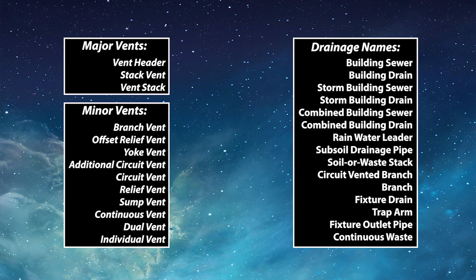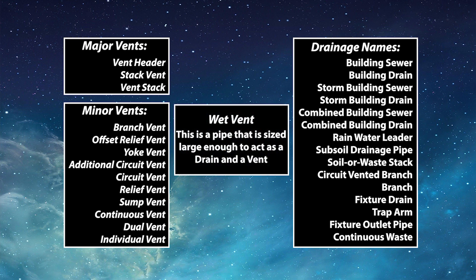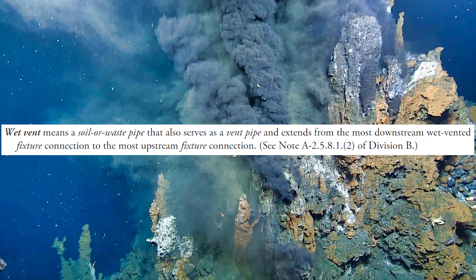In the plumbing trade we have many different types of drains and many different types of vents, but then we have one type of pipe that lands right in between the two. It's called the wet vent because it is a drain and a vent all built into one pipe. The code defines it this way: a wet vent means a soil waste pipe that also serves as a vent pipe, and extends from the most downstream wet vented fixture connection to the most upstream fixture connection.